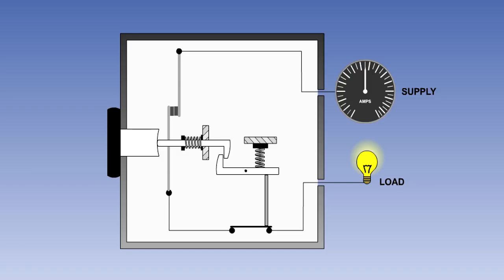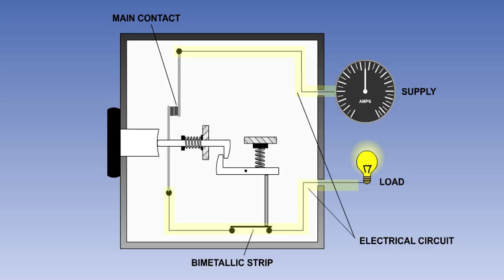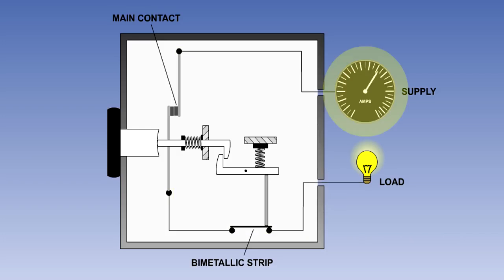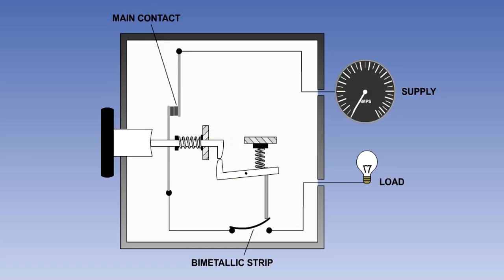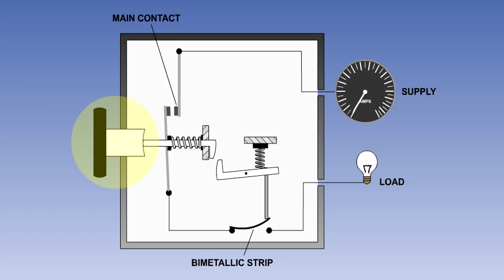In a typical trip-free circuit breaker, as shown here, a latch mechanism is being controlled by a thermosensitive tripping device, in this case a bimetallic strip. With the circuit breaker in the closed position, current flows through the main contacts, through the bimetallic strip and onto the load. If the current flow becomes excessive, the bimetallic strip will bend as shown, opening its contacts and releasing the latch mechanism. This action will open the main contacts and cause the push-pull button to pop out, exposing a white band on the button shank to aid identification of the tripped circuit breaker.